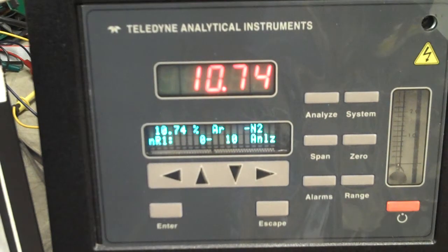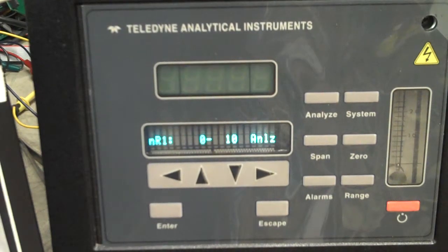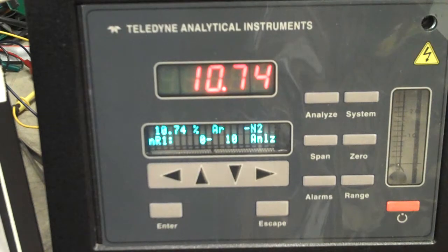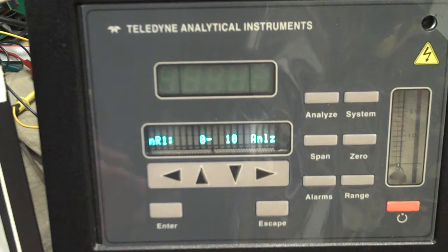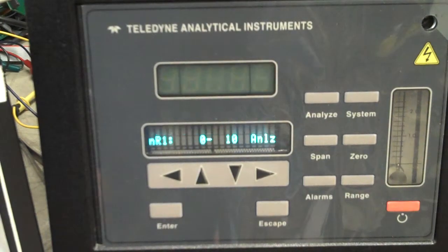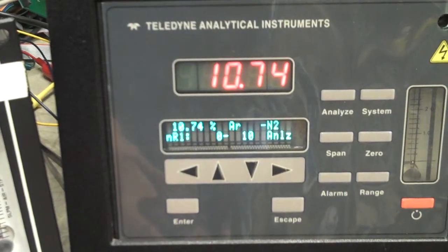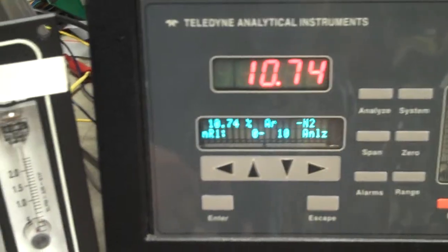So that's how it works on the 4060. You were selecting groups, different groups. In here we've got ranges. We have basically 3 ranges and a cal range. So you can select the range you want, and the range can have a different application. So basically I would say you have 3 ranges. The cal range is a special one that you use to calibrate the other 3 ranges.